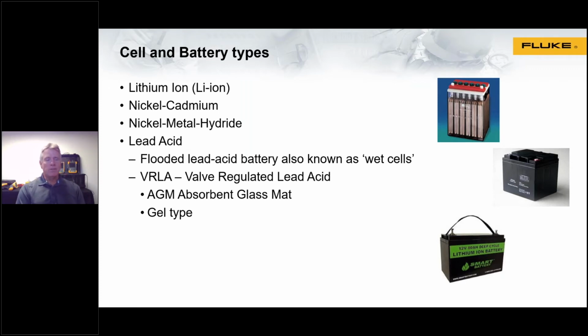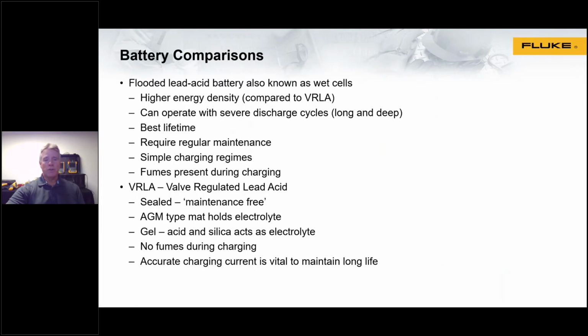Lead acid, that's the original battery technology. Really, it's the least expensive of all the technologies. They're very physically heavy, but they have a proven long life. They're very flexible and very useful for a wide variety of applications. A couple different types listed. One are called flooded lead acid batteries, or wet cells, essentially. And then what's referred to as a VRLA, or a valve regulated lead acid battery. And there's a couple different types of those listed there, the AGM and gel type batteries. So a wide variety of batteries that are out there, but all need to be tested to ensure that they're healthy.